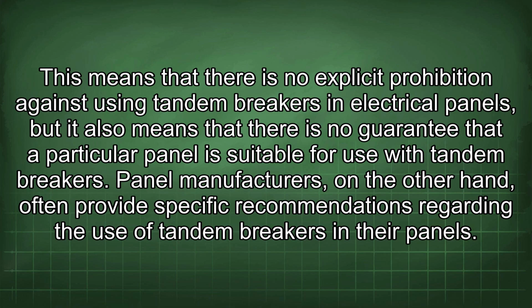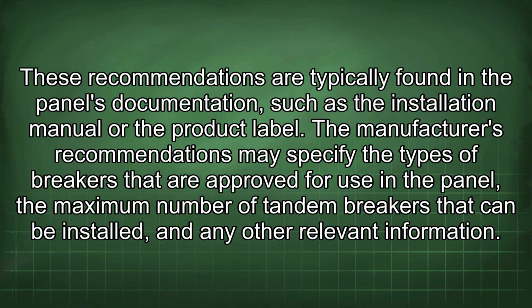Panel manufacturers, on the other hand, often provide specific recommendations regarding the use of tandem breakers in their panels. These recommendations are typically found in the panel's documentation, such as the installation manual or the product label. The manufacturer's recommendations may specify the types of breakers that are approved for use in the panel, the maximum number of tandem breakers that can be installed, and any other relevant information.